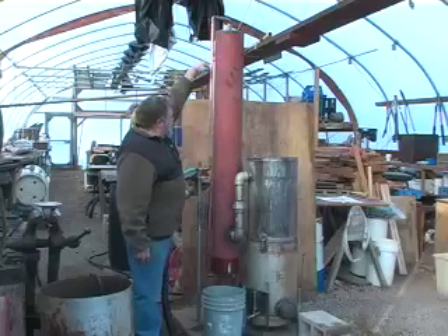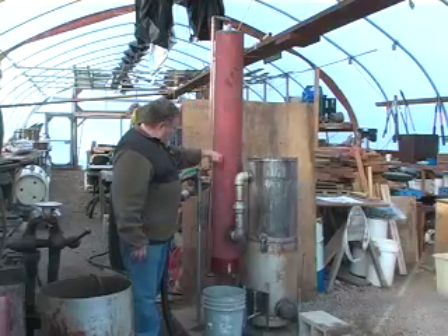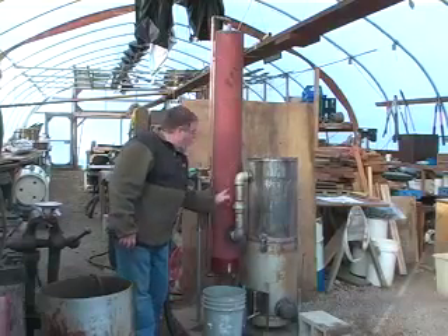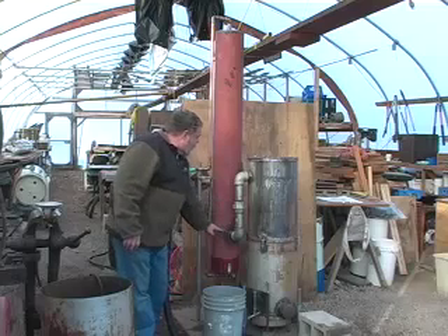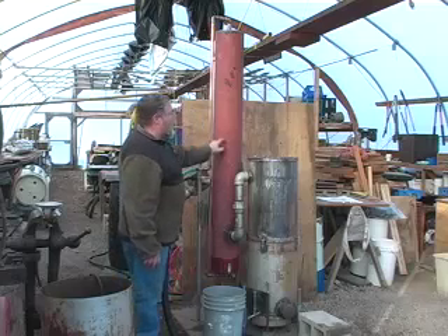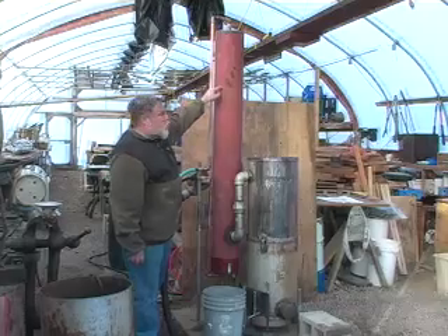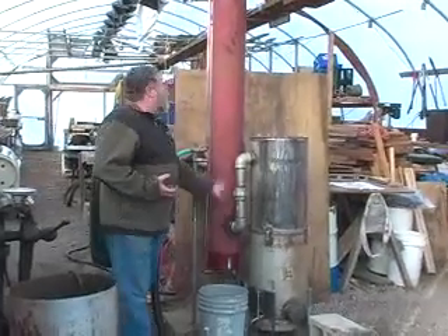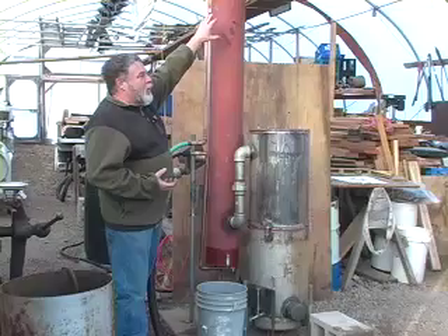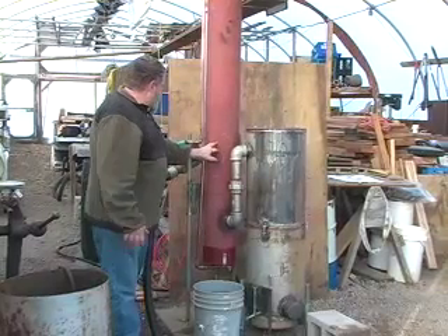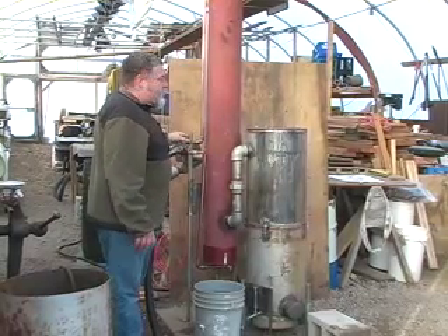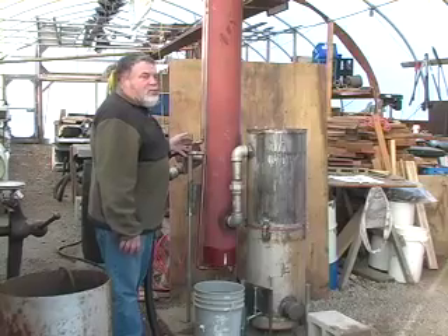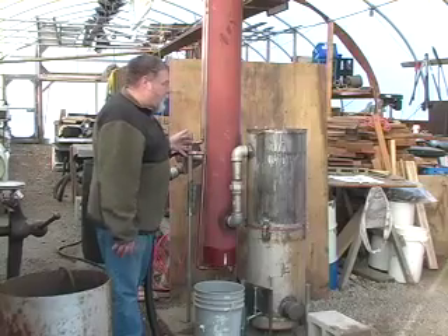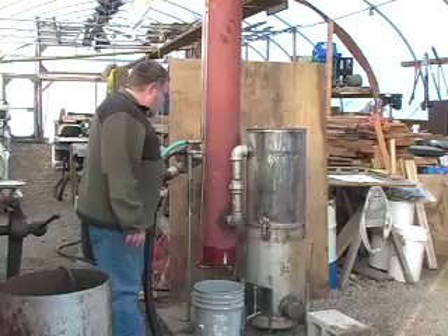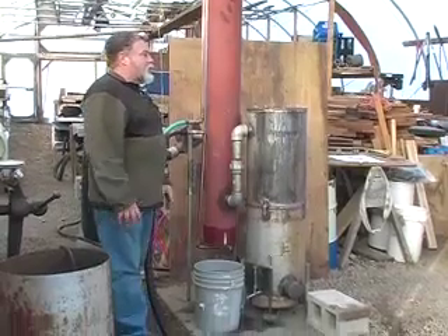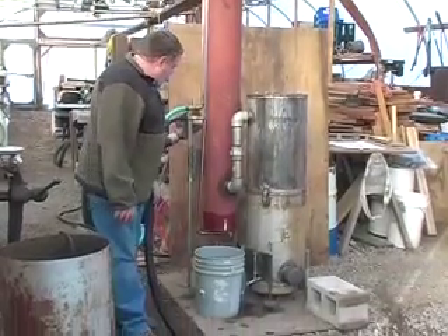Water goes up in the top, the cold water warms up as it's going all the way down to the bottom. The hot gas comes in at the bottom and is rising up at the same time past the coils. You have hot water, hot gas here. You have cold water, cold gas up here. So it's a counterflow design. We could easily reverse it and make it go the same way simply by reversing the flow of the water if we decide there's a reason to do that. But at this point I think it's probably prudent to keep the temperature ratios as close as we possibly can.